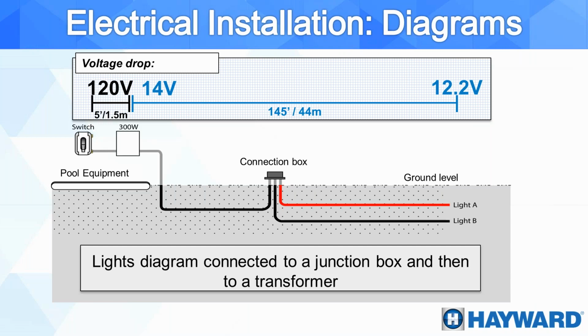And here we can see a couple of installations that show us how we can play around in order to get a safe installation. In this case, we have our light switch. We have a 300-watt transformer, and that 300-watt transformer is going to be feeding 14 volts, as we can see here. It's going to be feeding a junction box, and that junction box is going to be feeding 2 lights. Here we can see light A and light B. The maximum length that we can go from the transformer to the lights by using the 14-volt output on the transformer, we can see here, is 145 feet or 44 meters.